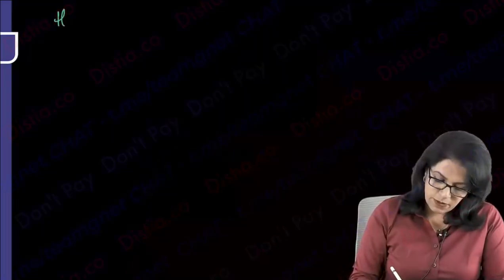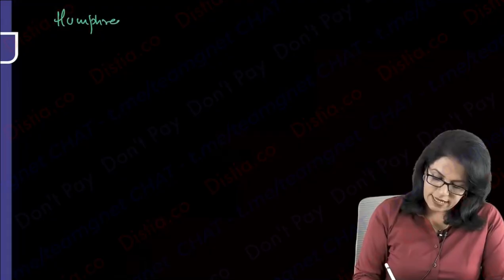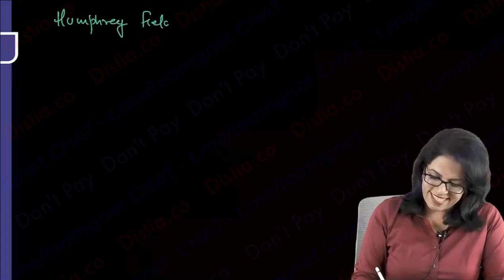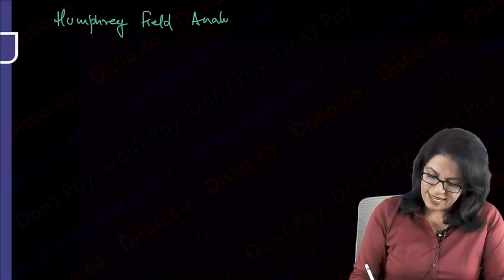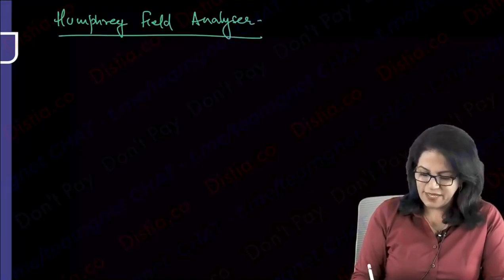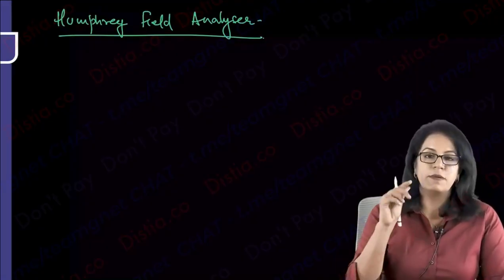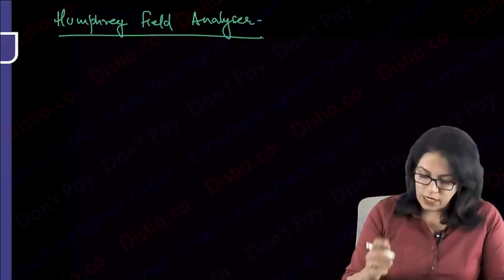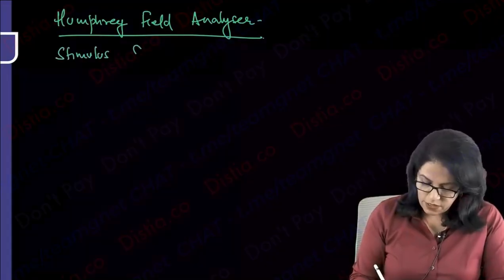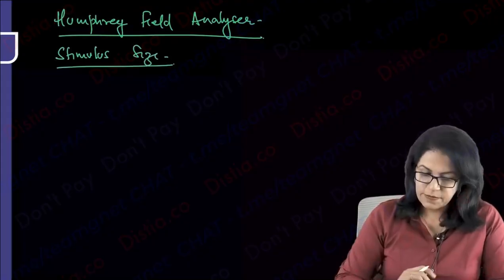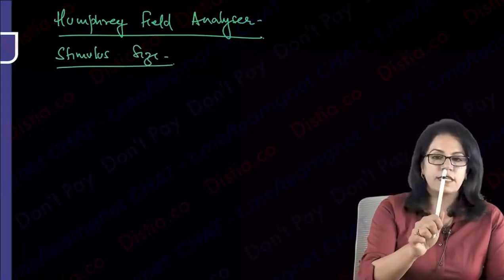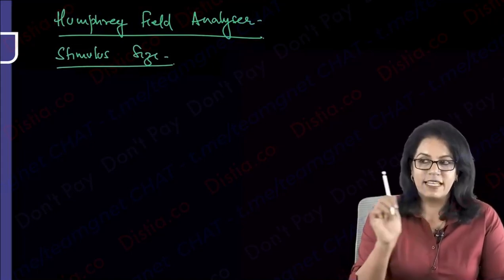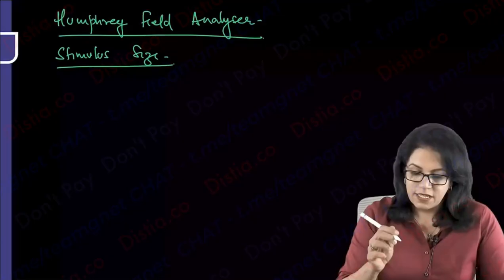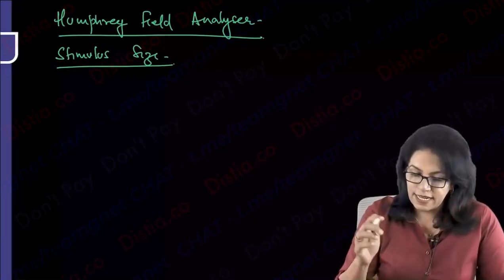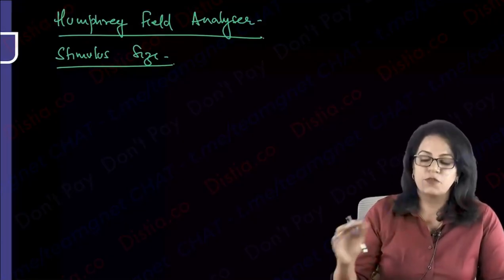So when you talk about the Humphrey field analyzer, there are a few things that I have to know. It's very interesting, so let's not panic. Let's try to understand what it is. There is a particular stimulus size, which has been standardized. The patient is fixing at the central fixation point, and different stimuli are given. The stimulus size in a Humphrey field analyzer is mainly in Roman numbers 1 to 5.